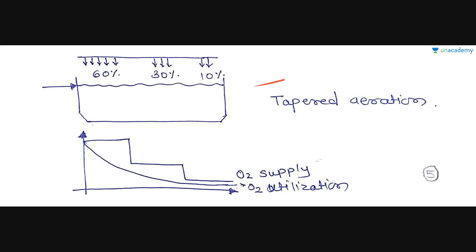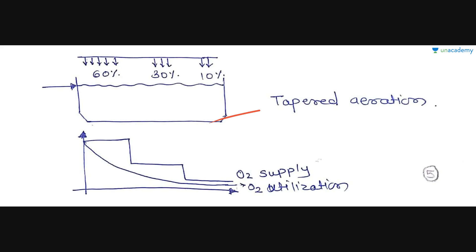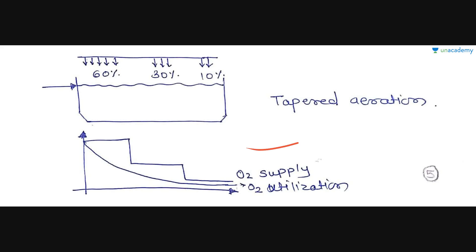In the tapered aeration process, higher oxygen supply is provided at the inlet and it gradually decreases as sewage moves towards the outlet. This process is based on the fact that as mixed liquor progresses through the aeration tank, its air requirement goes on reducing. Such a process therefore helps in ensuring optimal utilization of air in the aeration tank. So option D — tapered aeration — is the correct option for this question.